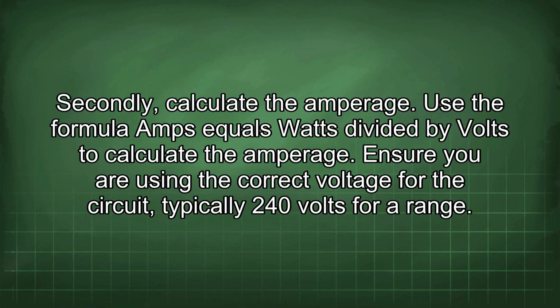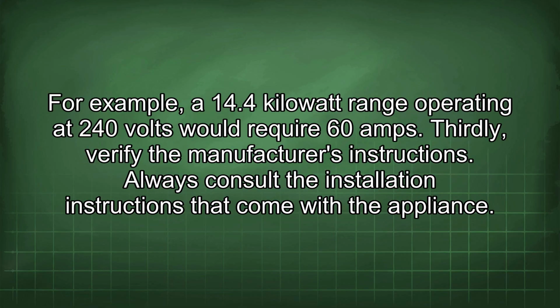Secondly, calculate the amperage. Use the formula amps equals watts divided by volts to calculate the amperage. Ensure you are using the correct voltage for the circuit, typically 240 volts for a range. For example, a 14.4 kilowatt range operating at 240 volts would require 60 amps.